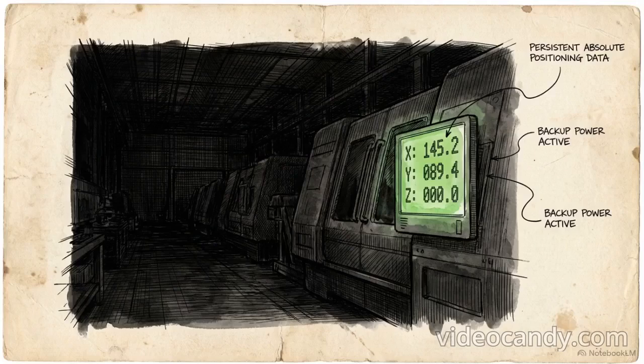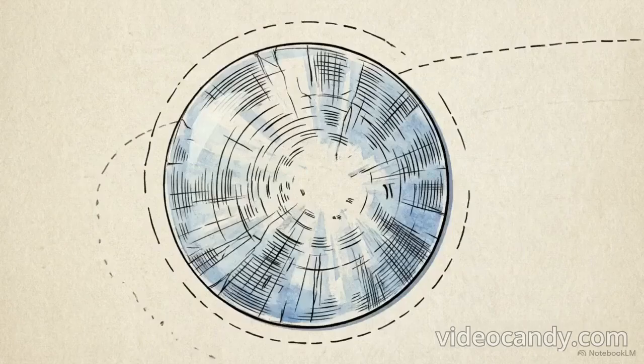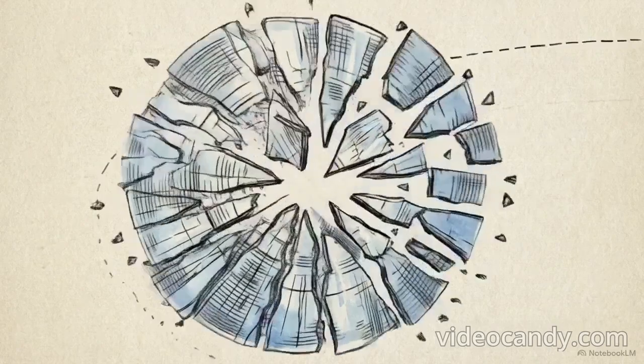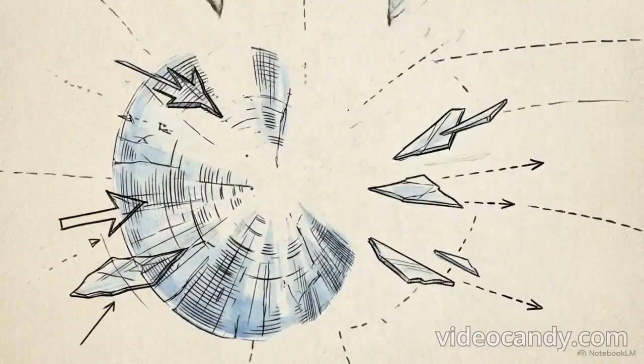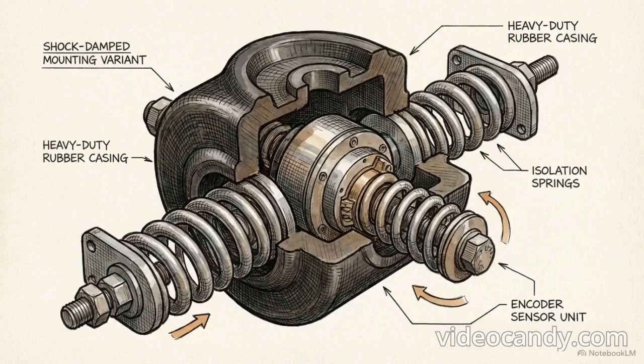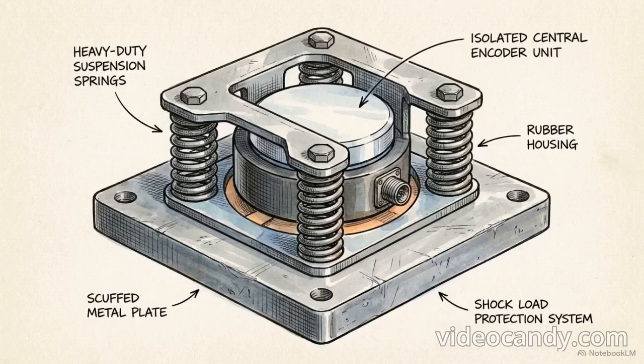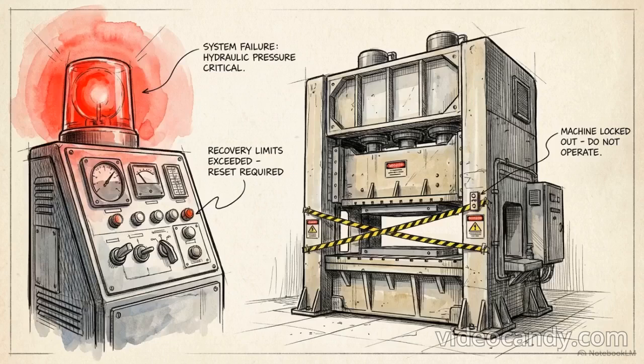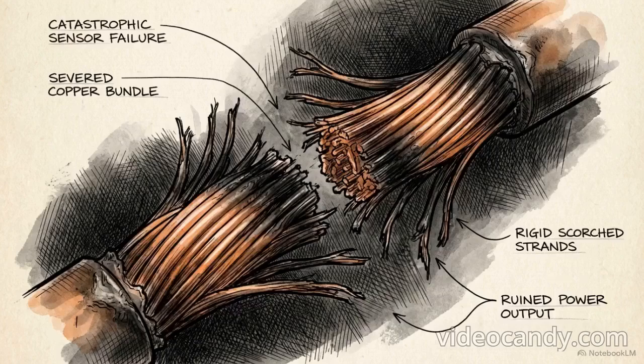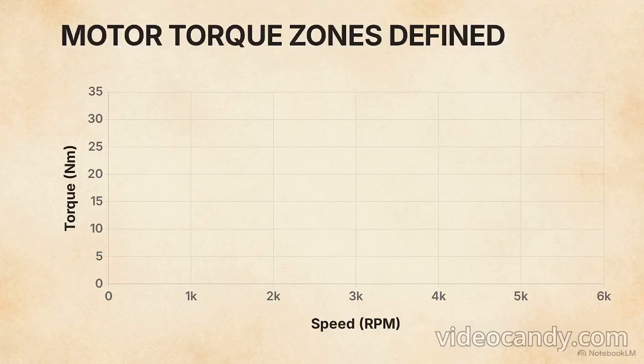Because absolute encoders constantly detect the exact physical position of the motor axis, they retain 24-bit position data even during a total blackout. They require zero restart calibration when the power returns. However, standard optical encoders contain fragile glass discs. Subjecting these to the violent shocks of heavy punch presses will cause the internal discs to shatter. To solve this, engineers must specify the shock-damped mounting encoder variant. This mechanical isolation is mandatory to protect the sensor from aggressive shock loads. Selecting the wrong encoder type or failing to protect it with proper mounting limits the machine's recovery speed and durability. If the sensor shatters, the motor's power output becomes unusable.